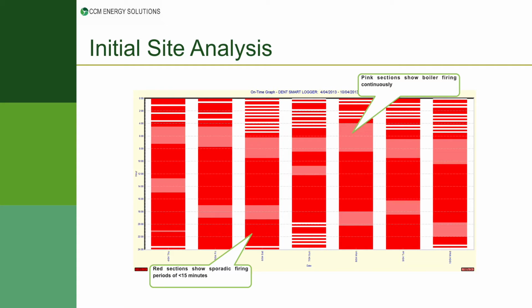As an initial site analysis, during the colder months, when the boiler turns on in the morning, it will run for a prolonged period to heat the building up. You see these pink sections here; that's when there is a genuine load on site, maybe the showers or heating for the building. After that period, the boiler turns on and off repetitively, or can, and this is data that we collect using a current logger on the gas valves. If I see this type of data with lots of red lines here, that means the boiler is turning on and off within a 15-minute period. That is where the M2G can make a significant difference.